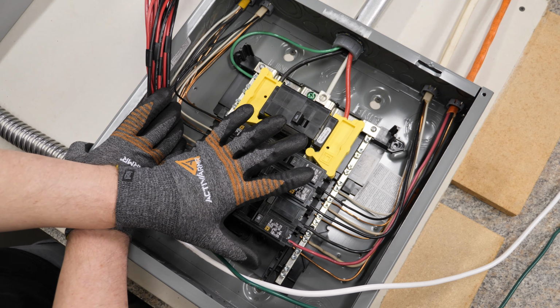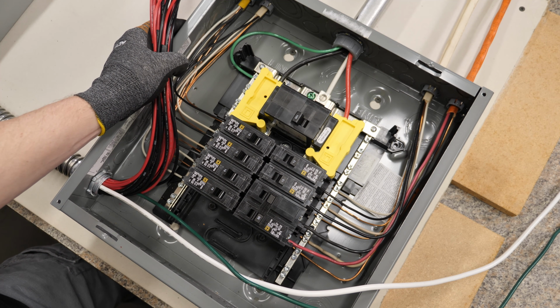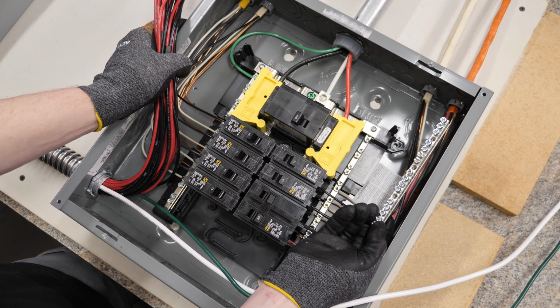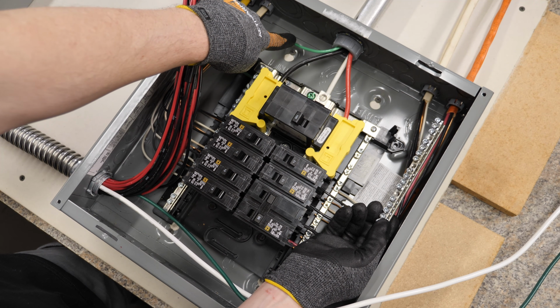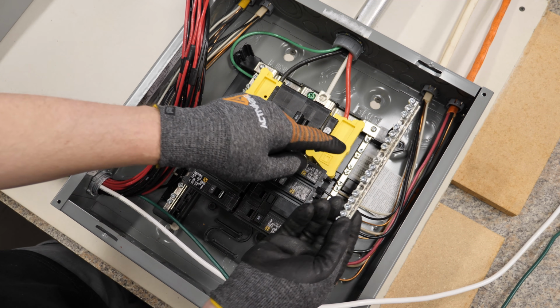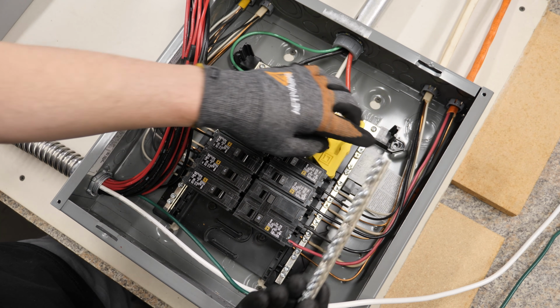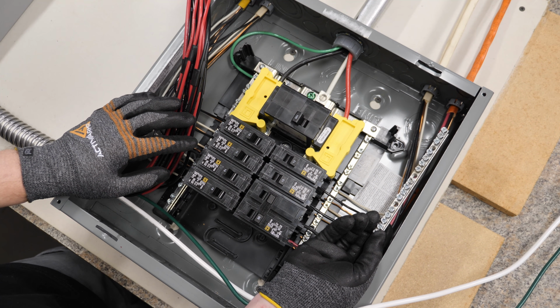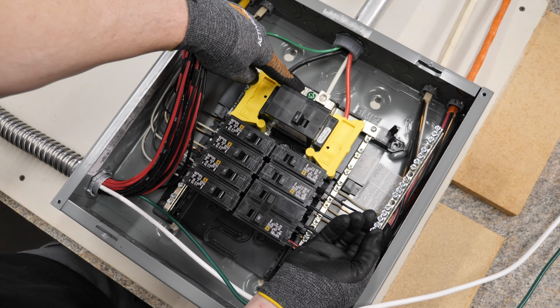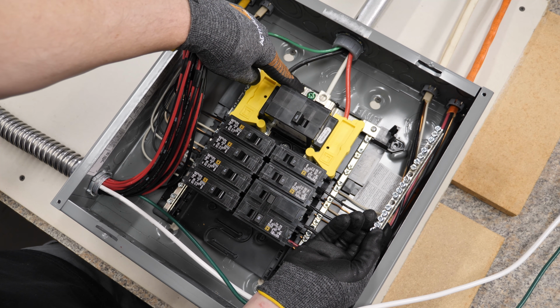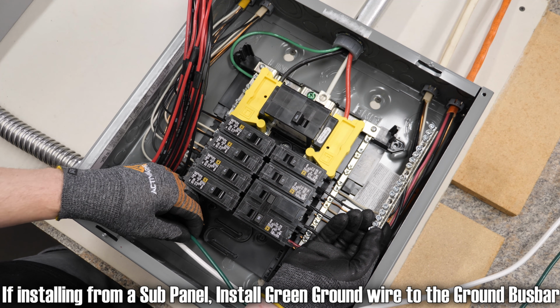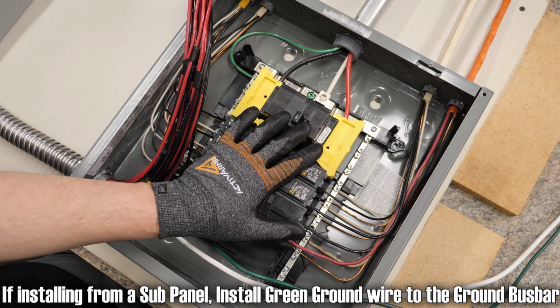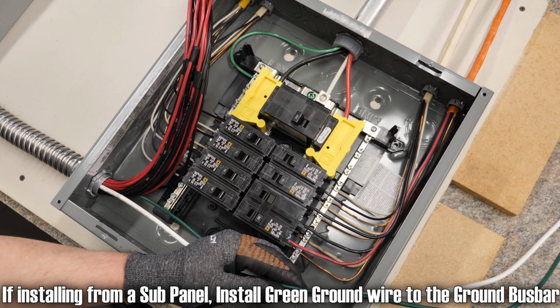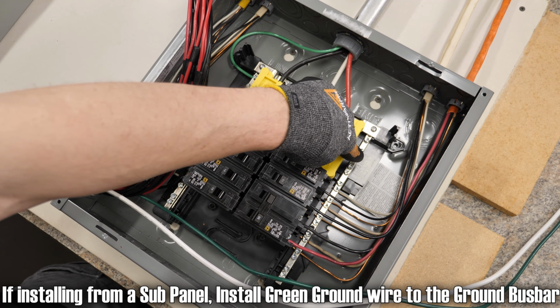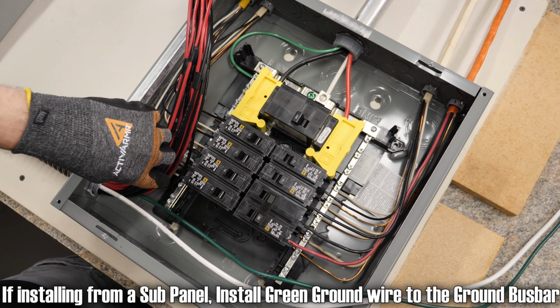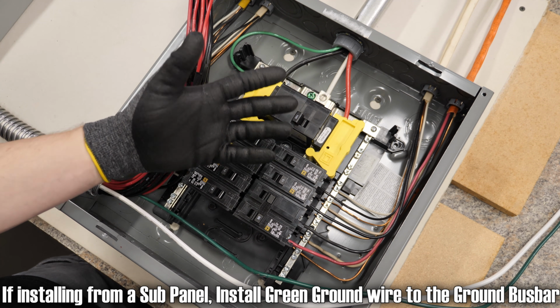If you're going to be powering stuff off of a sub panel, you're going to have a separate ground bar installed off to the side. Your green ground wire is going to be installed to the bus bar, same for all of your bare wires down here—all of those are going to be connected to the bus bar off to the side. Also, that green bond screw up here will be removed. The only thing that matters is where you install this green wire. Since mine is set up for a main panel configuration, I can install the green ground wire on this bar over here or on this bar over here. It doesn't really matter—it's just going to be whatever is convenient for you.